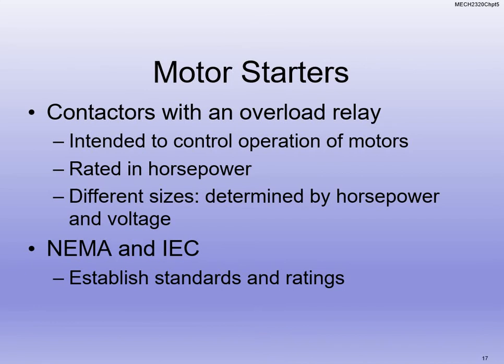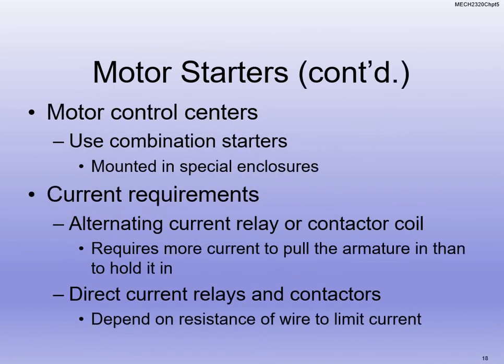There's a huge table in the NEC that you go through to determine what a 20-horsepower motor starter size should be, and you have to buy the right starter size because everything is rated based on current and voltage. That's not something you calculate — it's something you follow in the NEC, the National Electric Code. That's where NEMA and IEC come in with standards and ratings, all in conjunction with the NEC code.